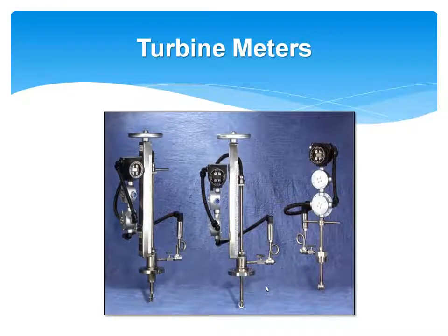Turbine flow meters are used to measure steam as well. Again, this is getting back to the reliability side. There are moving parts with this style of meter, and so you do need to be prepared to do some periodic maintenance on these meters, and that'll be a function of steam flow velocities and quality of steam and those types of things.